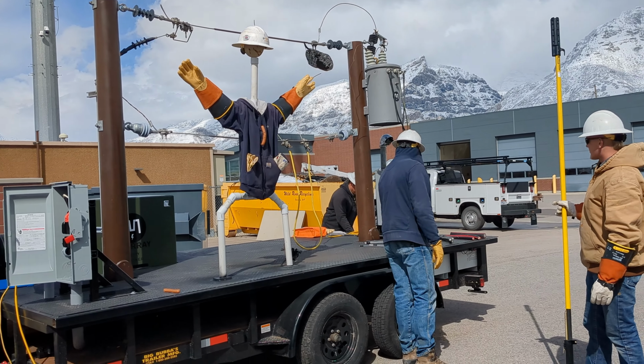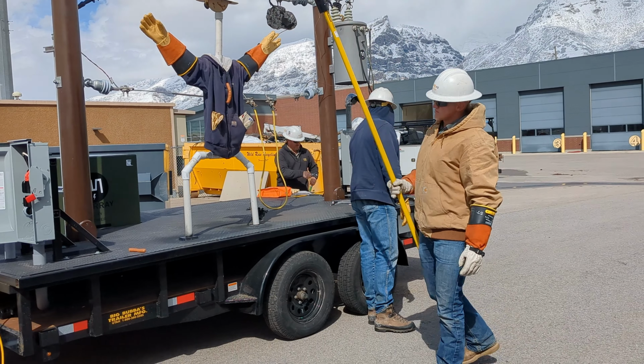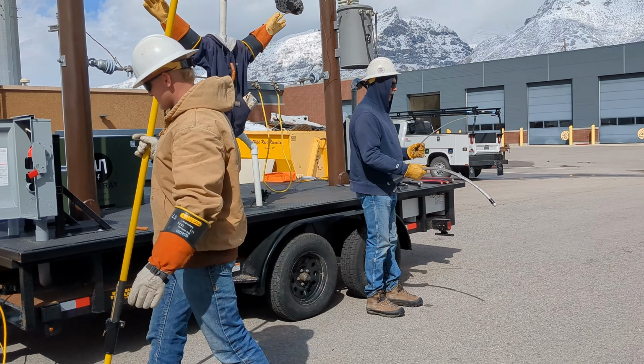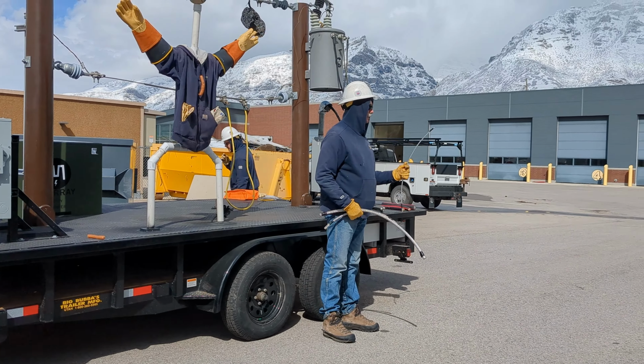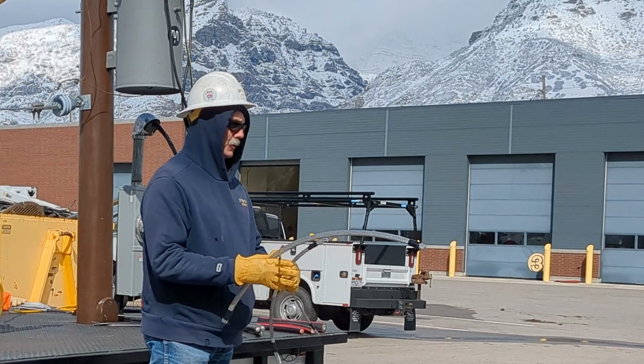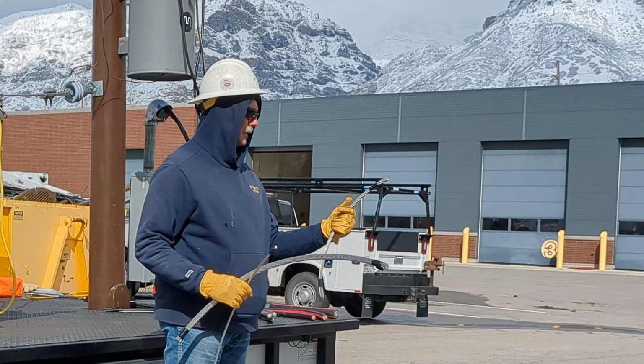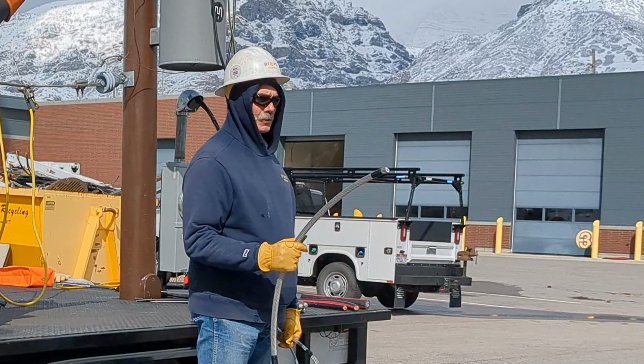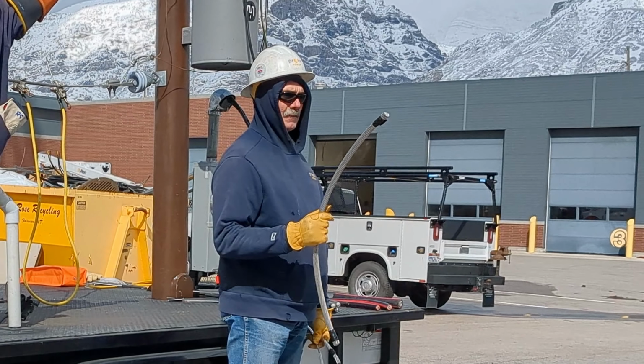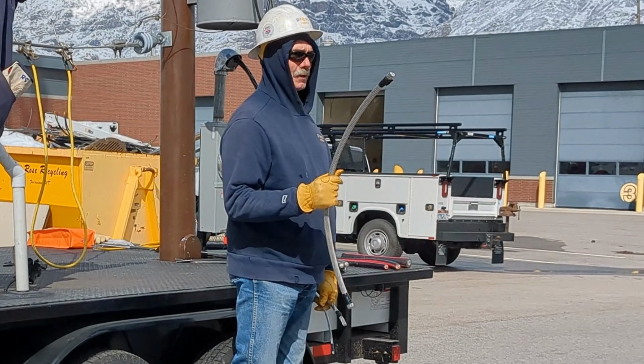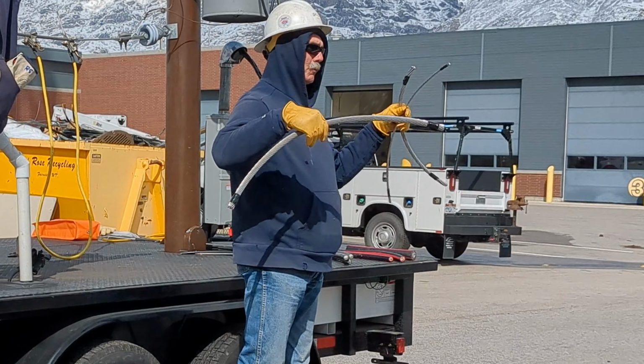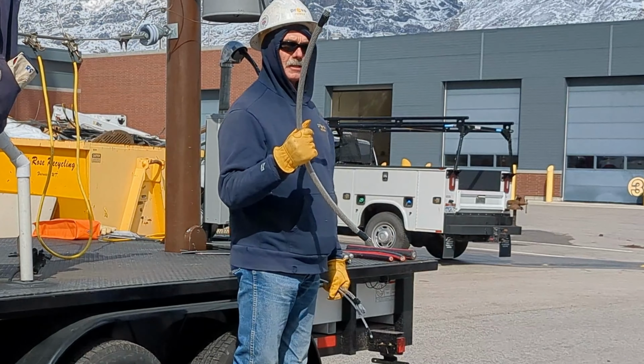These are the conductors we're using for our overhead lines. This is number 2 ACSR. And then we went to a 4-aught ACSR. And now we're using 477. And this is worth 600 amps. Just as our load just keeps moving up, we keep increasing the size.